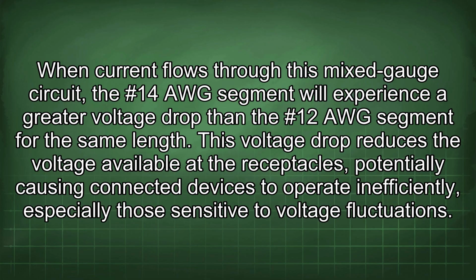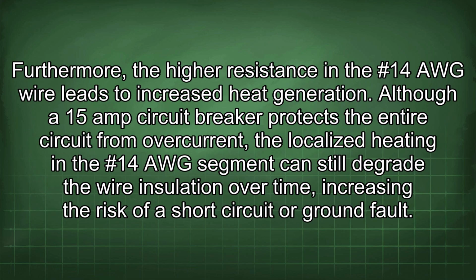When current flows through this mixed gauge circuit, the #14 AWG segment will experience a greater voltage drop than the #12 AWG segment for the same length. This voltage drop reduces the voltage available at the receptacles, potentially causing connected devices to operate inefficiently, especially those sensitive to voltage fluctuations. Furthermore, the higher resistance in the #14 AWG wire leads to increased heat generation. Although a 15 amp circuit breaker protects the entire circuit from overcurrent, the localized heating in the #14 AWG segment can still degrade the wire insulation over time, increasing the risk of a short circuit or ground fault.